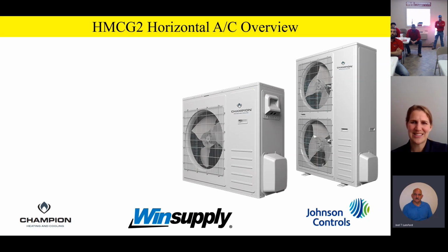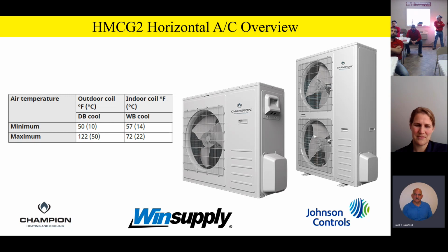All right, team, at this time, let's go ahead and jump into our HMCG2 horizontal overview. What this is going to be all about, it actually looks the same as the HMH7. It's just a straight cooling variant of the product. And remember, it comes in 2, 3, 4, and 5 ton variants. We have some pretty nice outdoor minimum and maximum temperatures, like we said before. On this particular product, it's 50 degrees minimum outside for cooling and 122 degrees outside for cooling. It's a straight cooling product, and again, that's a pretty nice temperature range.